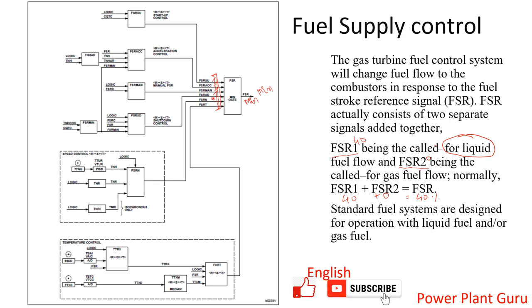Let's say you are operating your machine on dual fuel with total fuel of 100% requirement, then you are passing 20% from gas and 80% from liquid. That combination will be calculated and that will be passed through final FSR. Similarly if you operate only on gas then FSR 2 will be some value let's say 50% or 45% and FSR 1 will be 0. So this will be for gas firing, and FSR 1 will be for liquid fuel firing. If you are operating on dual fuel there will be some combination of FSR 1 and FSR 2.